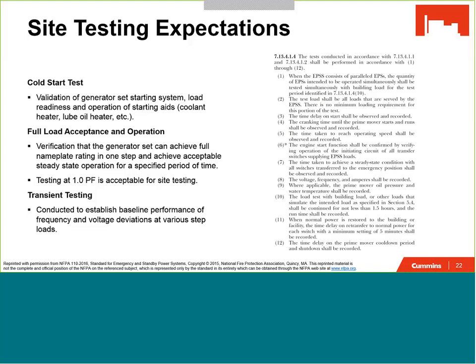For a rented load bank, a resistive load bank can, in many cases, be less expensive than a reactive load bank. So generally what most manufacturers would recommend is that testing with a purely resistive load bank at a 1.0 power factor is acceptable for on-site testing. Now, if you would like to see testing at 0.8 power factor on site, absolutely, go ahead and specify that. Just be aware that there may be additional cost implications with that type of testing.